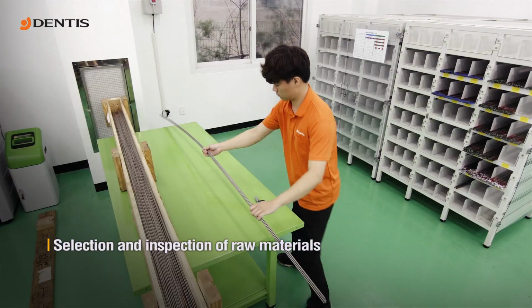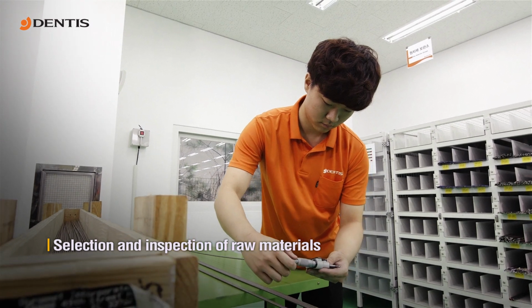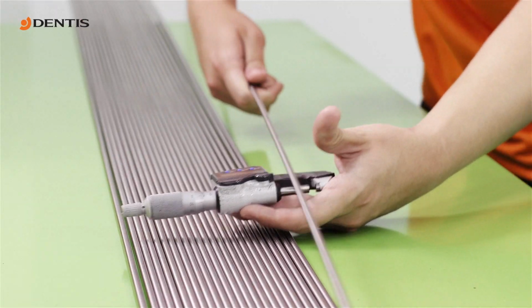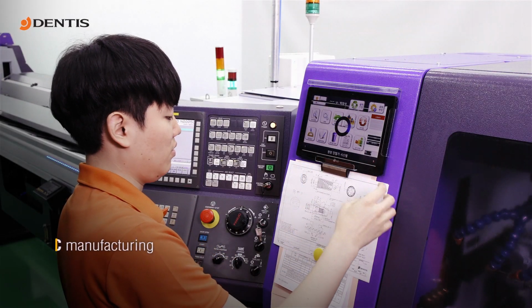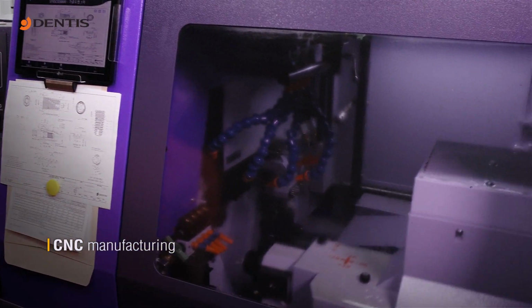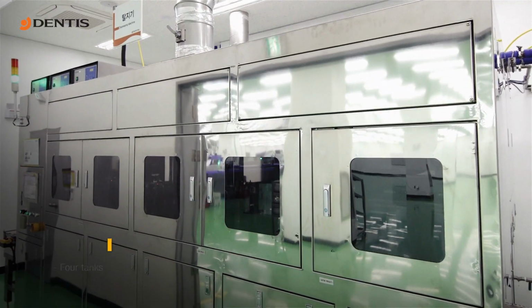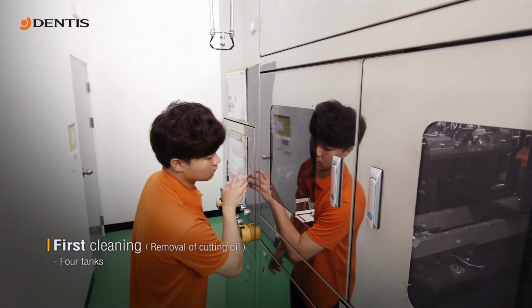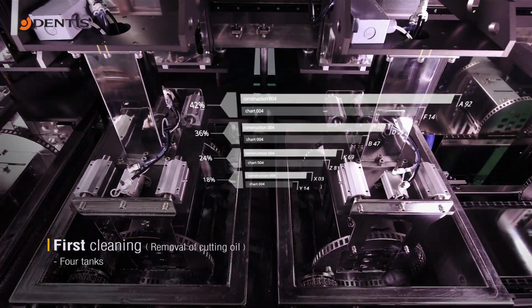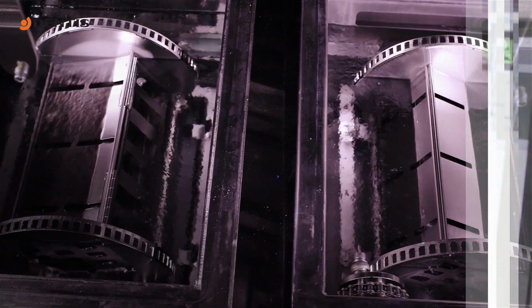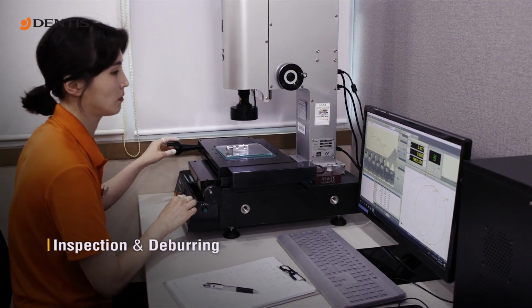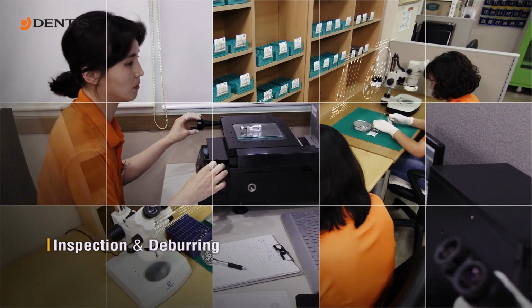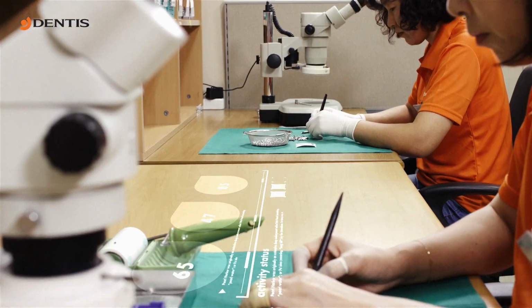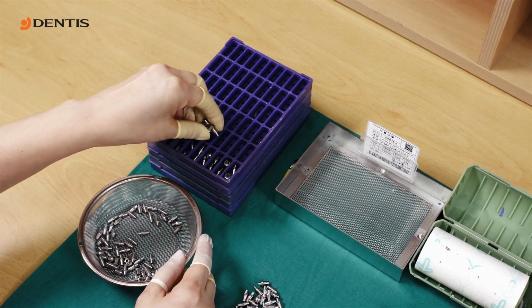The DENTIS implant cleaning process begins after selection and inspection of quality raw materials such as titanium. The implants are manufactured by CNC by an automated process. And the first cleaning, in 4 tanks, is done to remove cutting oil. A sample of the cleaned implants is inspected under a microscope and by precision measurement equipment.